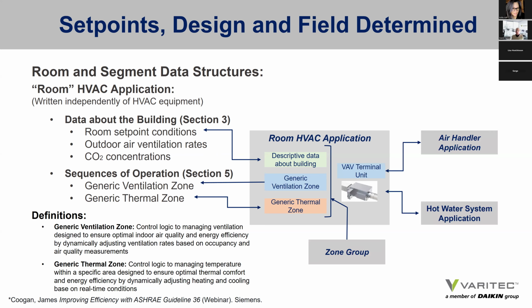Also within that space, in a VAV system certainly, and the logic applies as well to fan coil units, chilled beams, fan power terminal units, is the actual device, the HVAC device that is responding to the local load and making the adjustments it needs to maintain the conditions that are called out in the room designations shown on the left. So all of this is interconnected and data is exchanged not only from the VAV terminal with the amount of airflow going through the terminal back to the air handler, but also from the air handler and the BAS to the VAV box that allows control and override of temperatures from that VAV box.